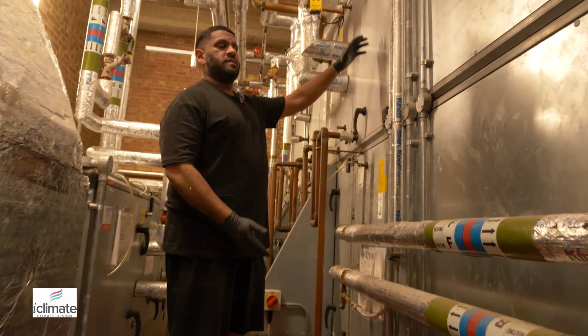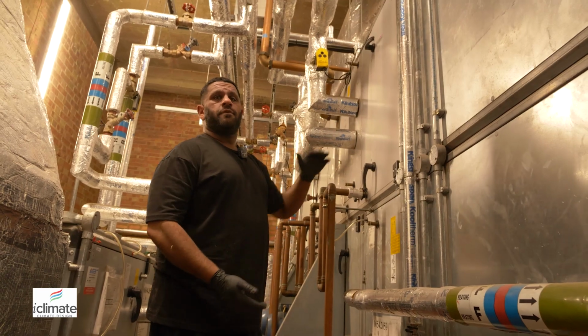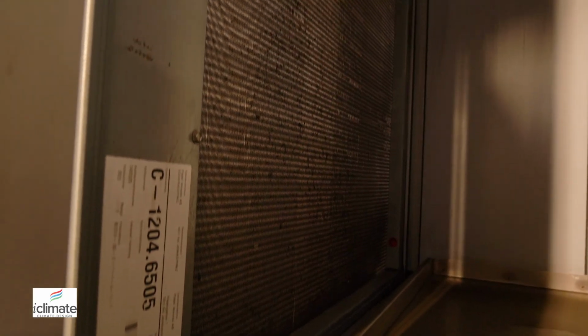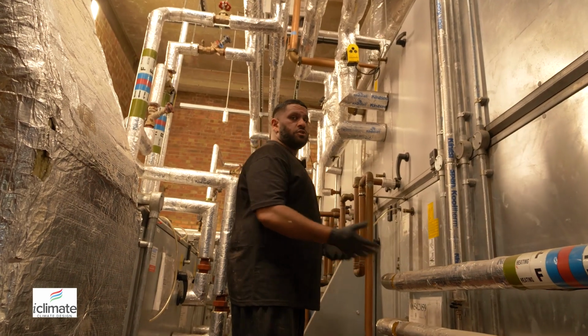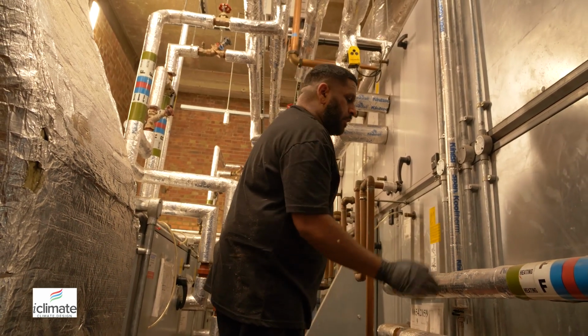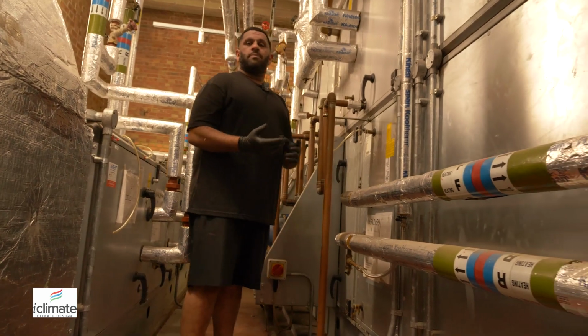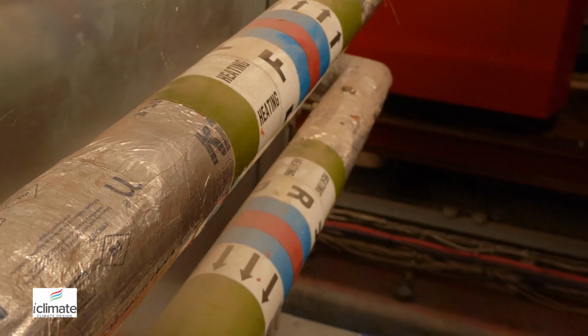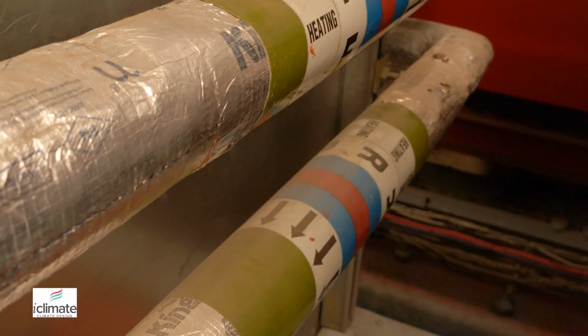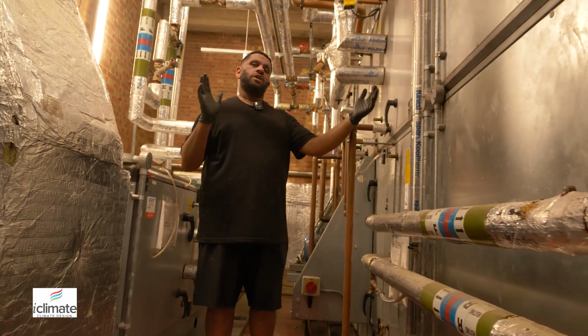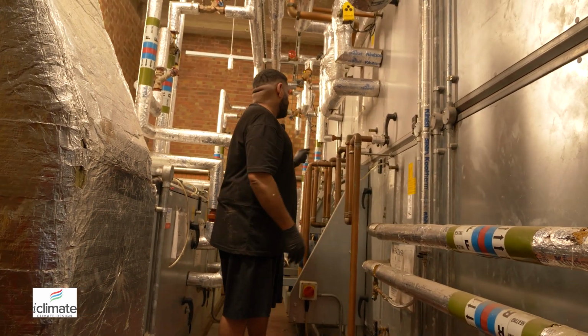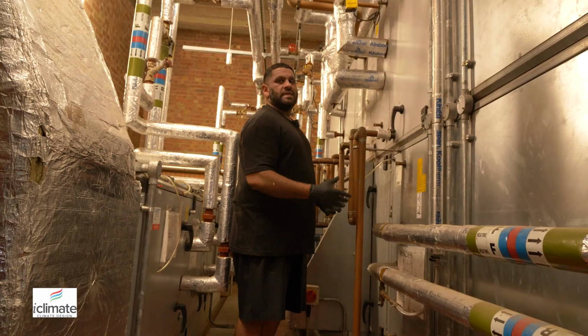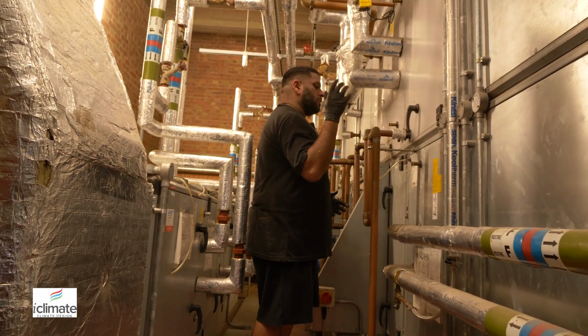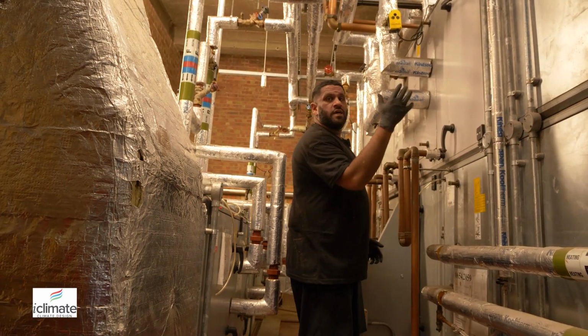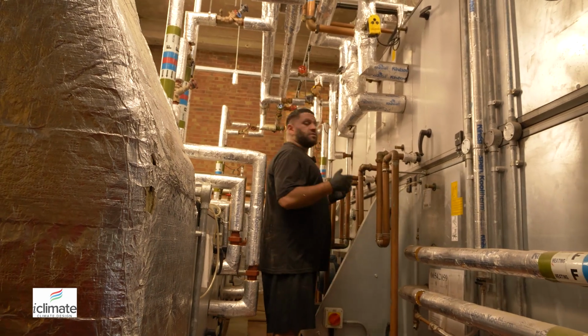Very large compartments that are responsible for moving air from the building, conditioning it, filtering it, and sending it through the ductwork in the building to the right spaces, right? So these are large chambers of air. The pipework connecting to the chambers provides heating, and if it has a red band on it, it says heating, flow and return into here. They have very large heat exchangers sitting within the chambers, and as the fans move the air across in heating, they'll provide a temperature difference and gain the heat, lose the heat from the water to the air, providing us heating, and vice versa in cooling.